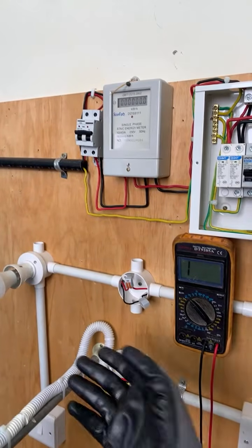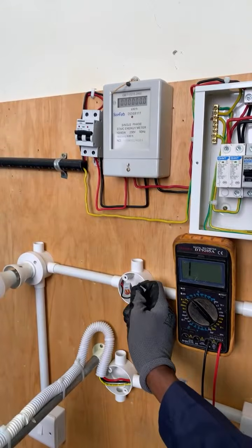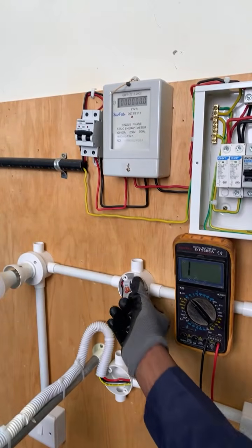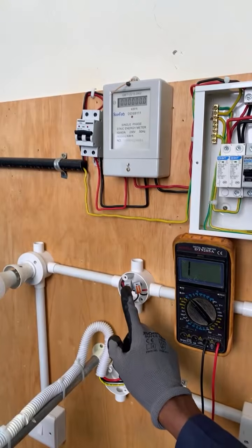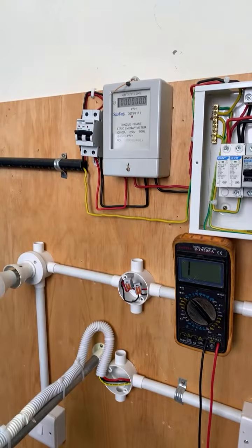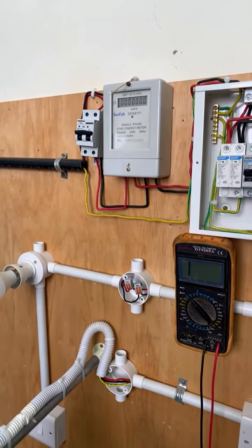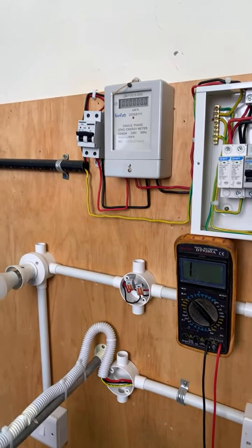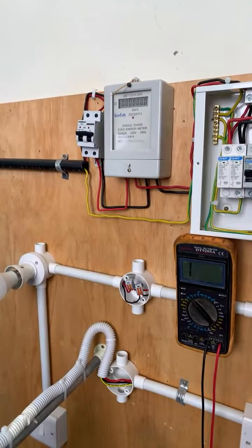Assuming that this house has a ceiling in it, and assuming that we don't have these WAGO connectors, the connection that has been done there is wires that have been jointed, bundled or twisted together, with insulation tape that is not really insulating the cables.